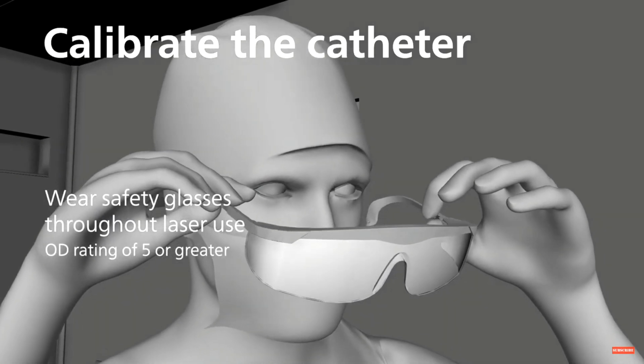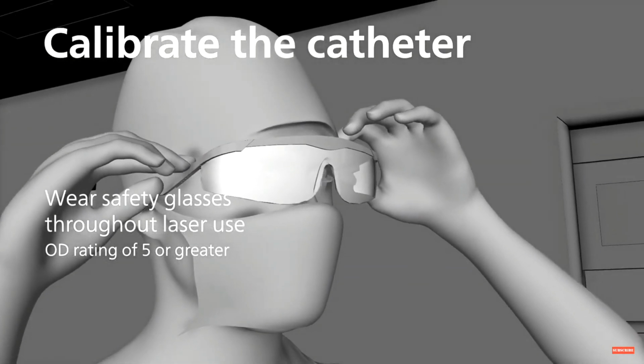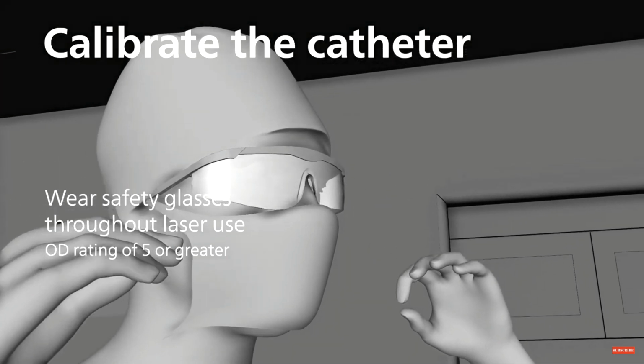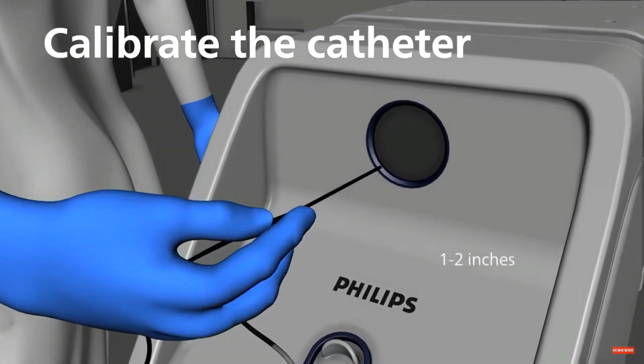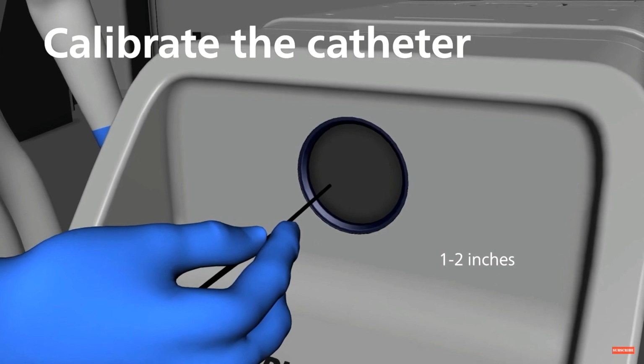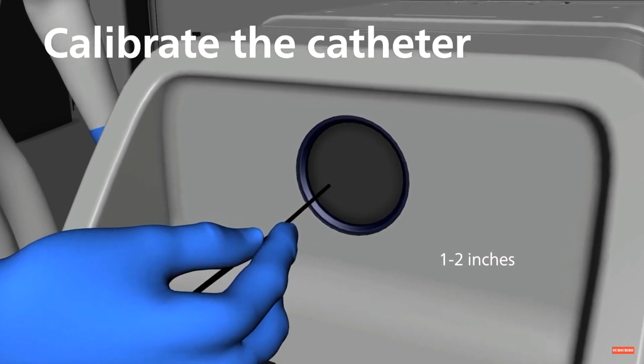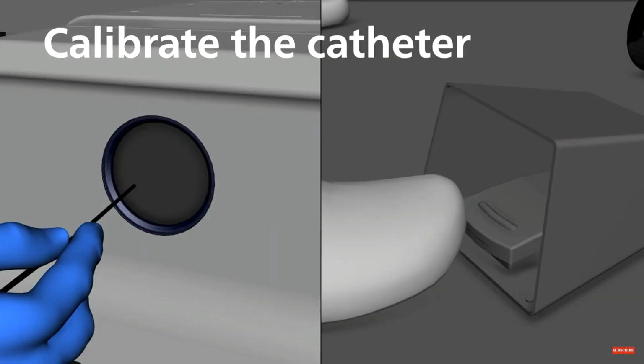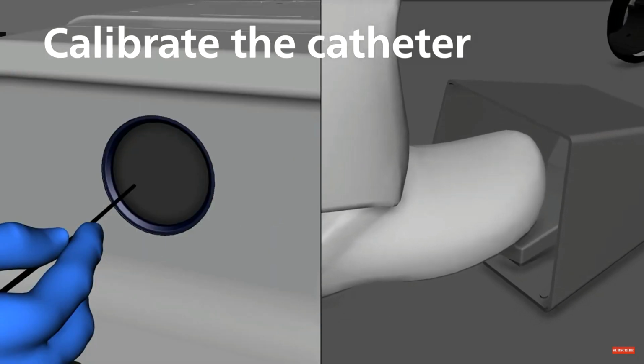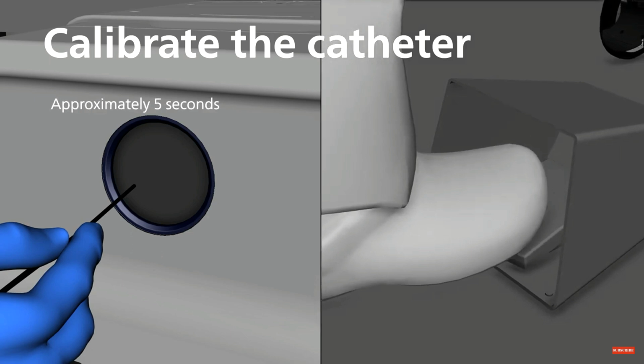Wear safety glasses with an OD rating of 5 or greater while laser is in use, including while calibrating the catheter. Point the distal tip of the fiber optic catheter directly at the center of the energy detector. Ensure the catheter placement is no less than 1 inch or 2.5 centimeters, and no more than 2 inches or 5 centimeters away from the front surface. The end of the catheter will illuminate with a red light to aid in aiming the catheter. Depress the foot switch until calibration is complete. This will take approximately 5 seconds.